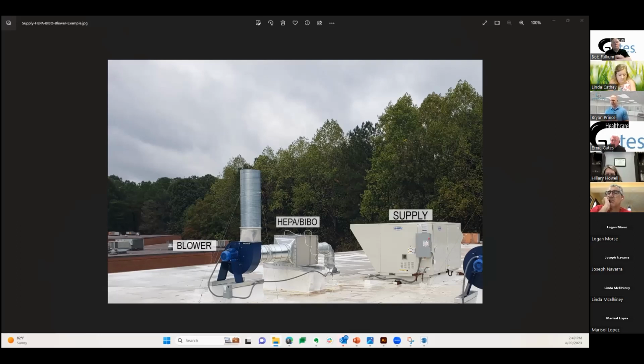On the negative side, we talked a little bit about this with the biological safety cabinets, you can make the space too big. The bigger you make the space, the more air that's got to get pumped volumetrically out of the room, out of the building, and then volumetrically you've got to replace that. That's when it becomes an energy hog. So I would tell you to put some logic into it. You could design, let's say you've got one biological safety cabinet, and ask, is it possible I could grow to a second one? Yes. So instead of maybe a 6-footer next time, maybe I've already got a 6-footer, maybe I put in a 4-footer next time.